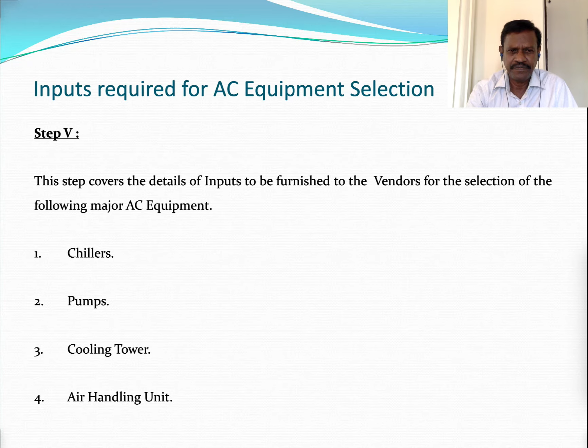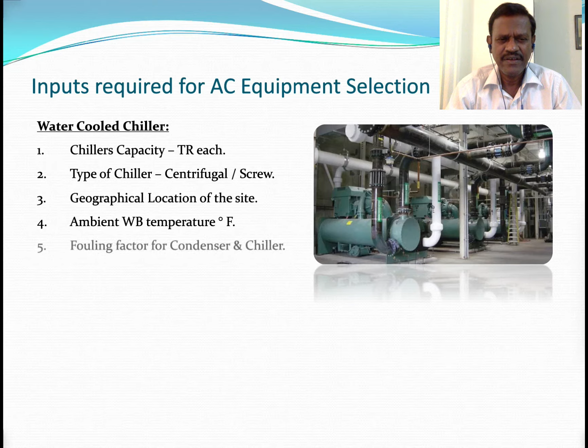You have to specify the chiller capacity in TR, what capacity you require for each chiller, and the number of chillers. Specify the type of chiller, whether you want centrifugal or screw. Then tell the vendor the geographical location of the site, the ambient wet bulb temperature, the fouling factor for condenser and chiller, and the power supply you are planning, whether LT or HT.